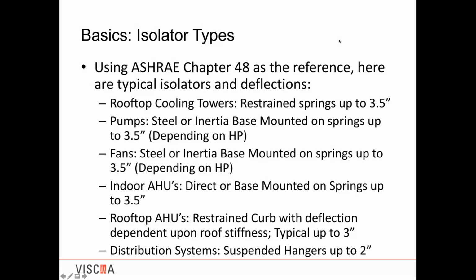And with rooftop cooling towers, it's extremely important that the framing underneath, whether it's called a dunnage frame or grillage frame, the stiffness of that is very important because these cooling towers get large and heavy, and the spans of these beams get relatively large. So if you're doing the analysis with an improper support structure, picking the 3.5-inch deflection might not even work for you. The stiffness of that support structure is very similar to looking at the stiffness of the building slab. If the building slab is a spring itself, you have a double mass system. And then it goes well beyond the basics, outside of the scope of this particular course.